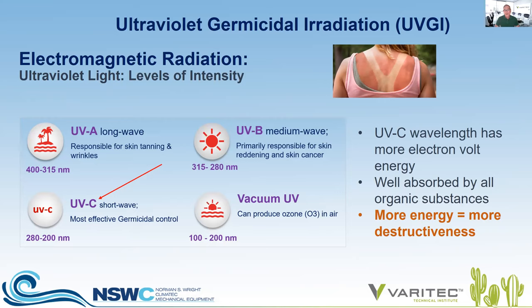Just as there are ranges of energy along the electromagnetic spectrum, there are ranges within UV light. UVA long-wave light is responsible for skin tanning and wrinkles, between 315 and 400 nanometers. UVB medium-wave light is responsible for skin reddening, sunburn, and skin cancer. UVC light, our focus today, ranges between 200 and 280 nanometers and is most effective for germicidal control — it's like a key going in a lock. Then there is vacuum UV light at 100 to 200 nanometers, at which you can actually create ozone.